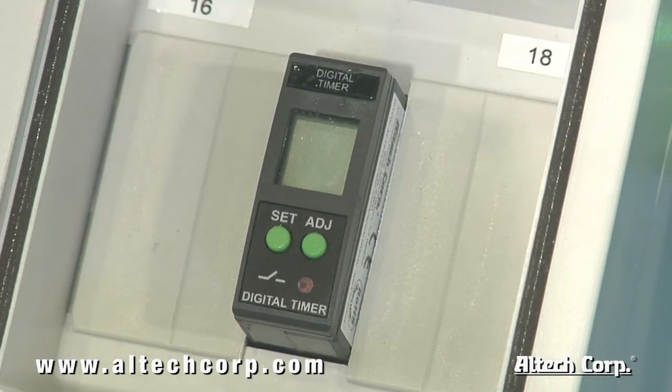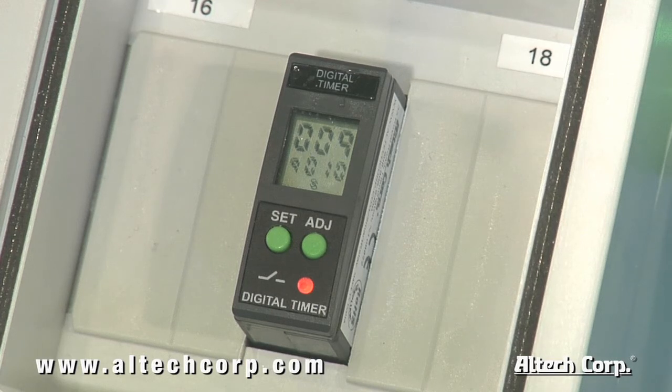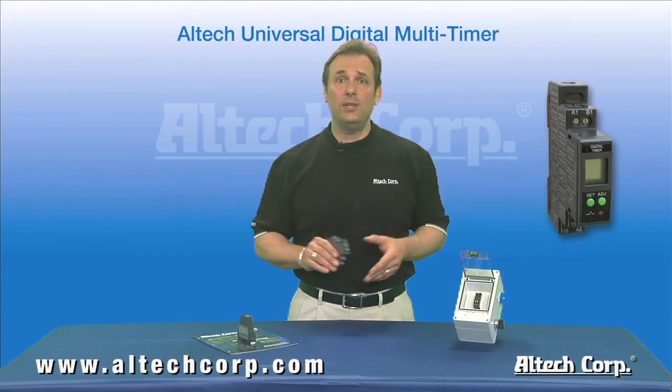Utilizing the programming that we just completed, our timer will operate in a signal-off delay after 10 seconds. Powering on the Altech multi-timer — after triggering the off delay, the output state LED on the front of the unit will show the output contact is on, and the display will show the 10-second countdown. After 10 seconds, the timer will open the output contact. Very simple and easy to use.